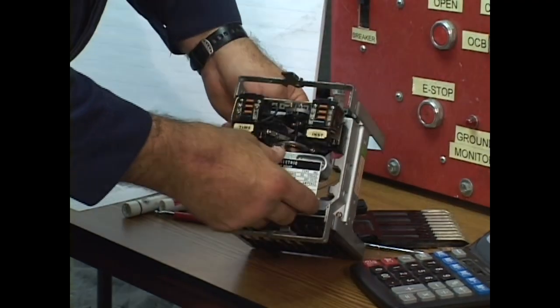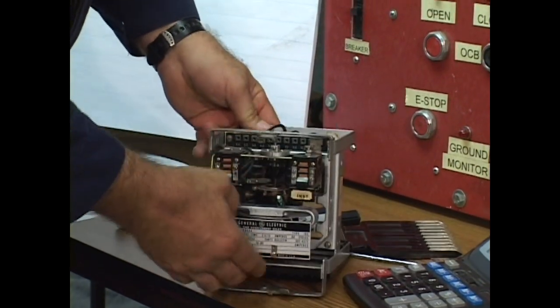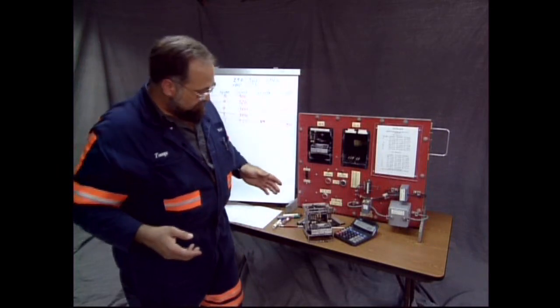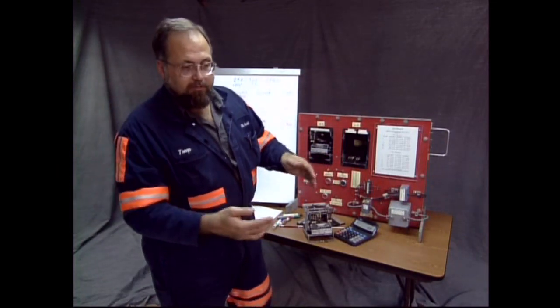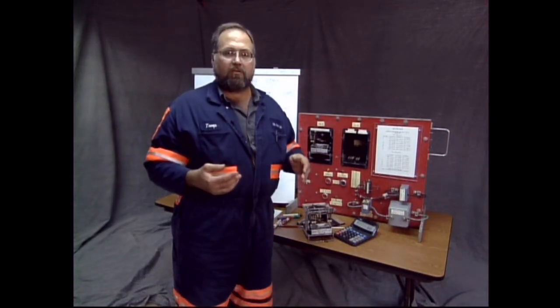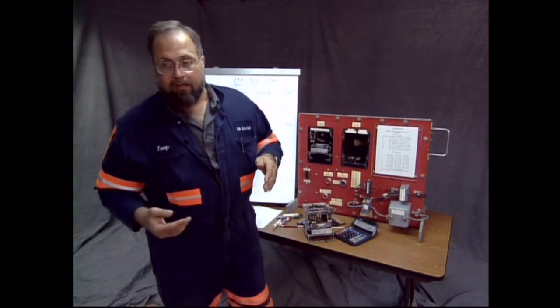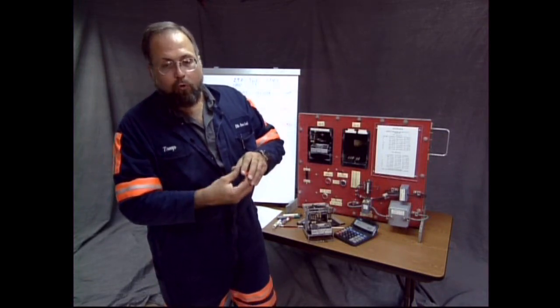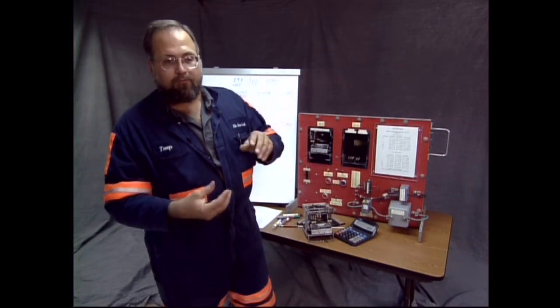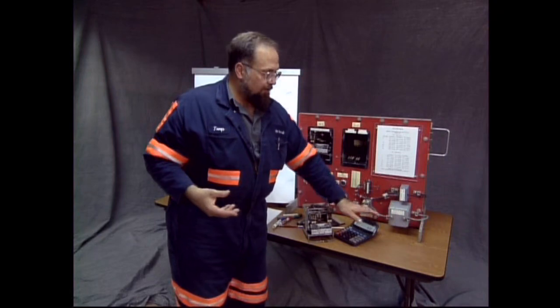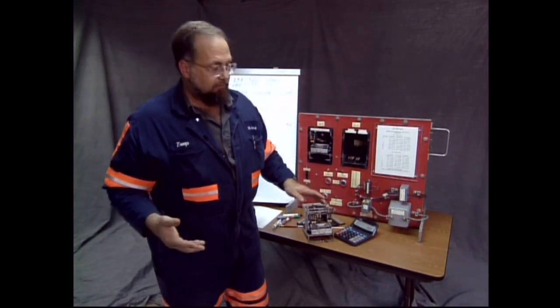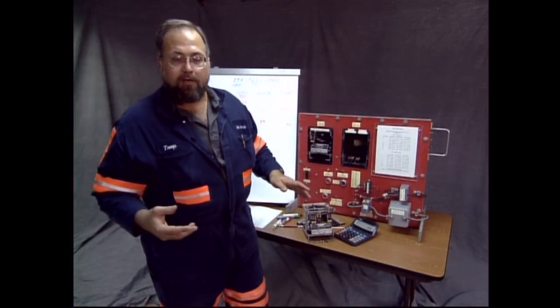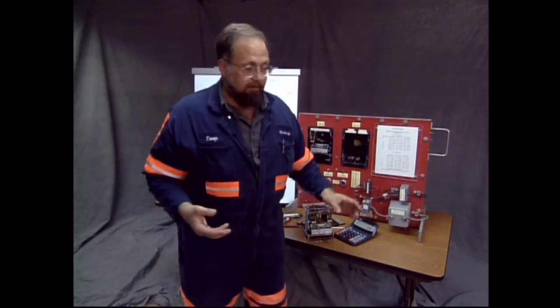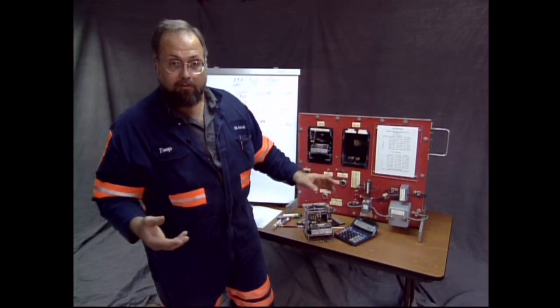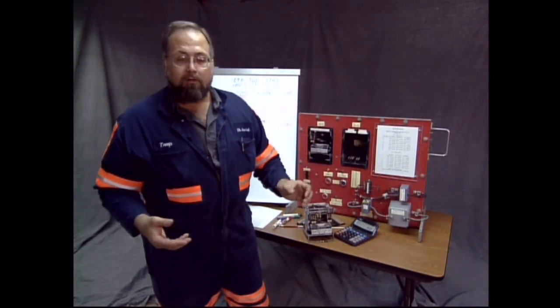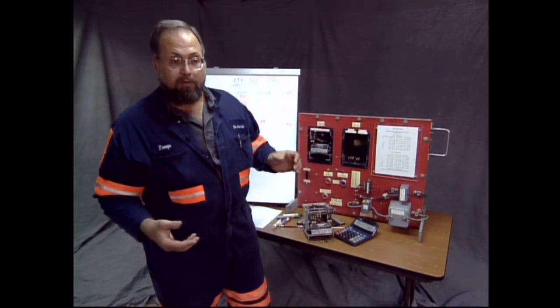This is an adjustable core relay. You know from our prior classes that we've talked about magnetism. To make an electromagnet, each energized conductor has a magnetic field that constantly surrounds it while it's energized. And to focus this magnetism, you can put a core into the magnet, and that gives a more defined magnetism. Same effect as if you would take sunlight on a piece of paper. Sunlight in and of itself will fade the paper over time, might make it yellow or color it somehow, but it won't consume it. But if you focus that sunlight through a magnifying glass, it will burn a hole in the paper. Well, having a core in a coil will focus the magnetism and make it much more powerful.